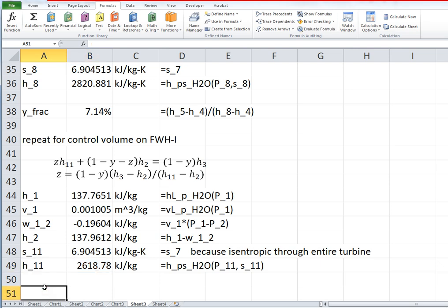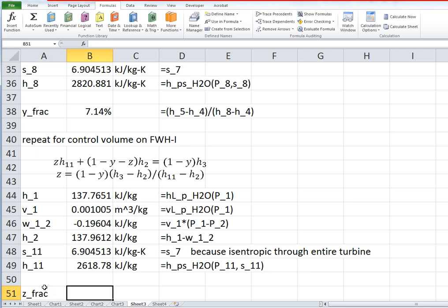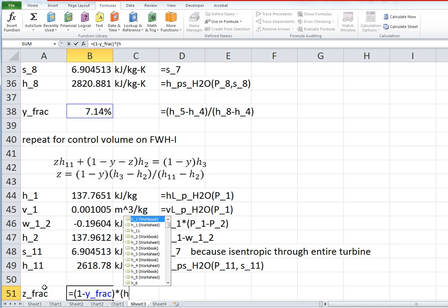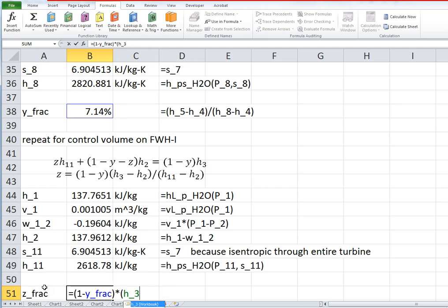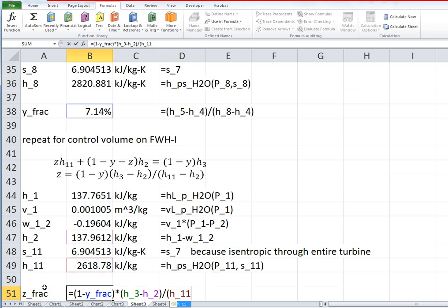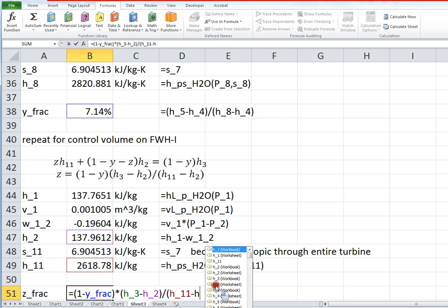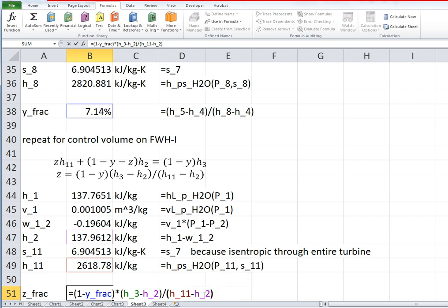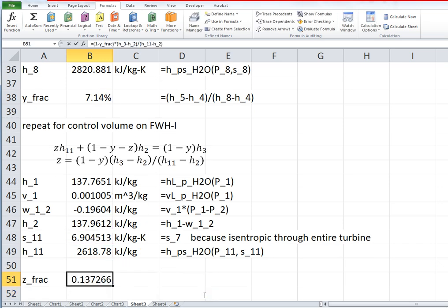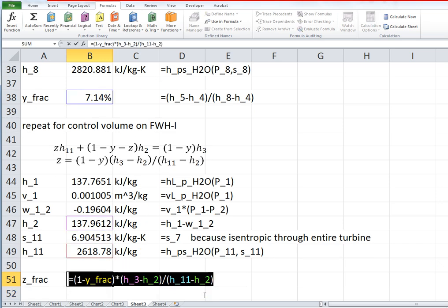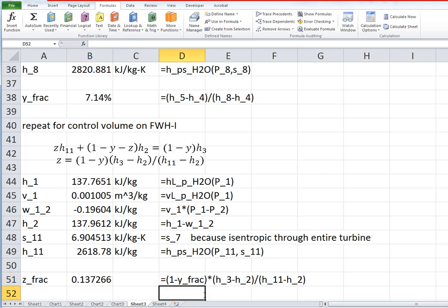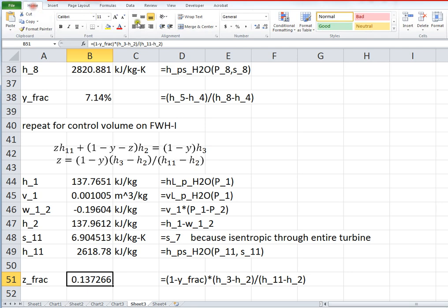The z fraction is equal to 1 minus the y fraction times h3 minus h2 divided by h11 minus h2. And we come up with about 13%, so it's a much bigger fraction of steam that's taken out at that point.